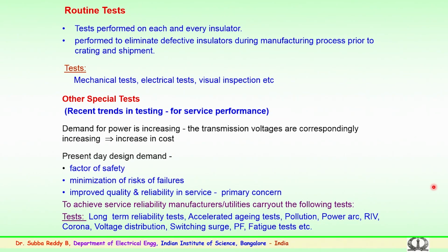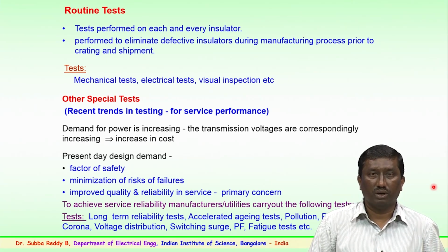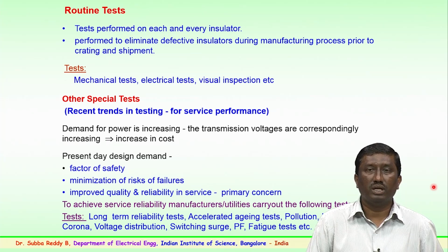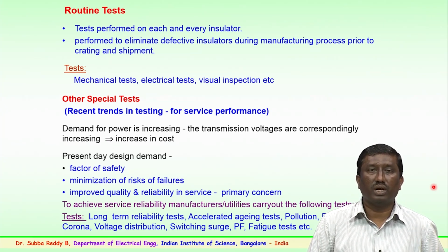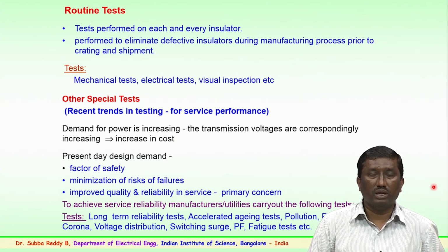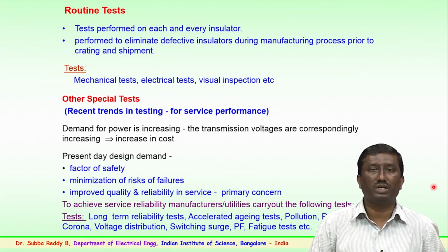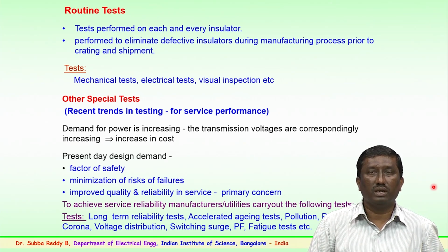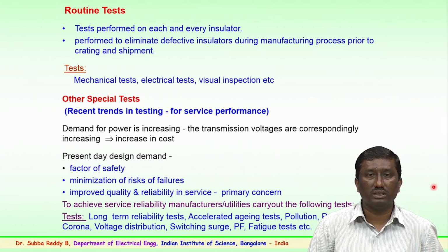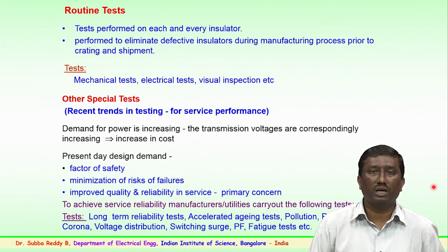The third category is the routine test. As mentioned earlier, routine tests are performed on each and every insulator. In the factory, these are performed mainly to eliminate defective insulators during the manufacturing process, prior to crating and shipment. If these routine tests are not carried out on every sample, there is a likelihood that some insulators may be defective, which could again see failure in the field. So the routine test has to be performed on every sample. The tests include mechanical tests, some electrical tests, visual inspection and so on. These are the three categories of tests specified as important verification methods for the insulator string.